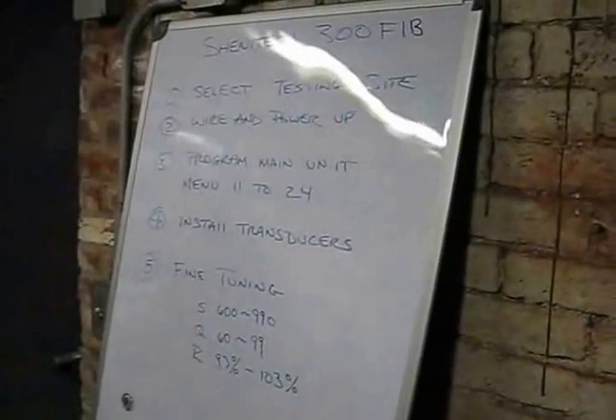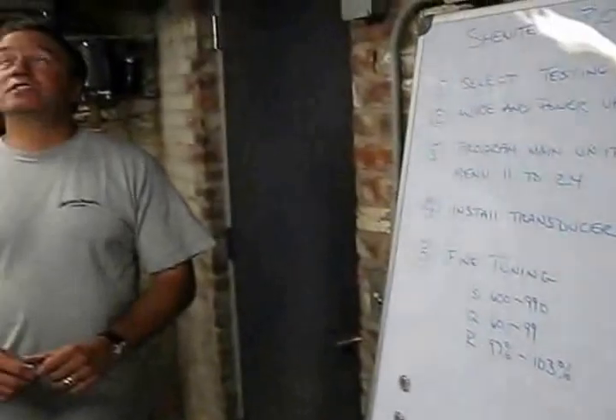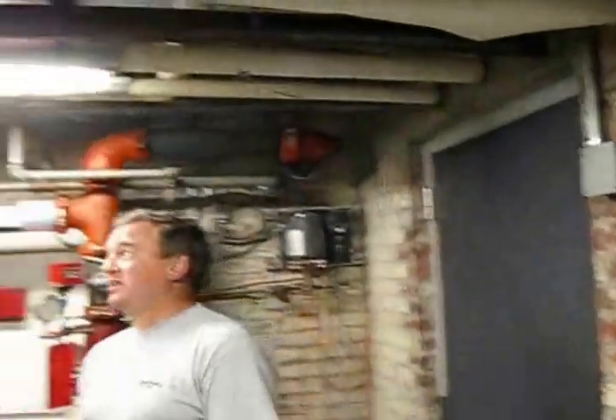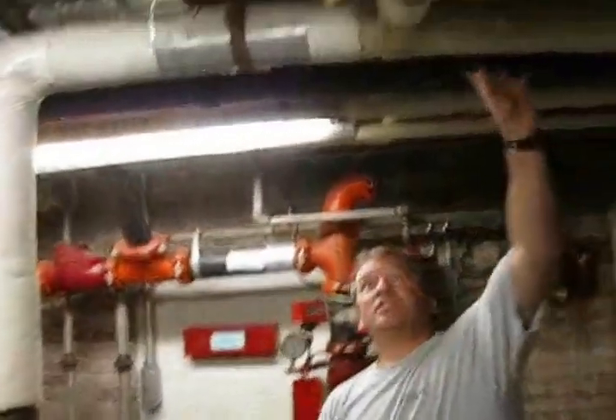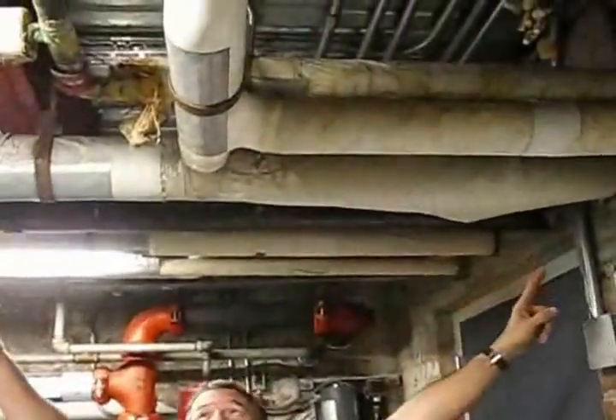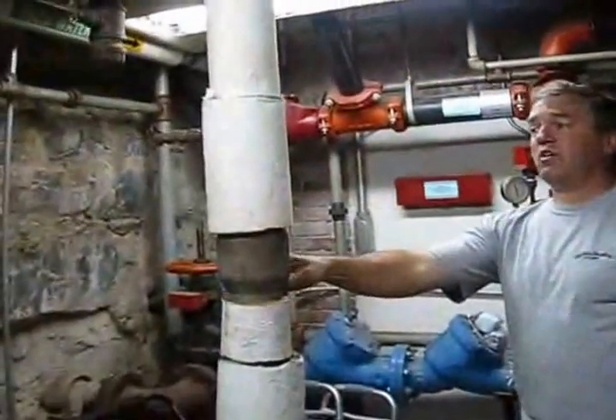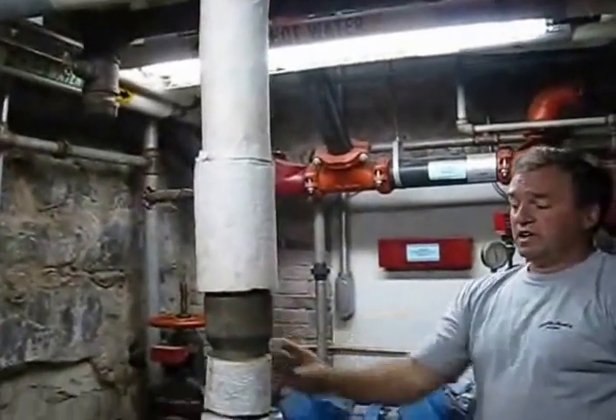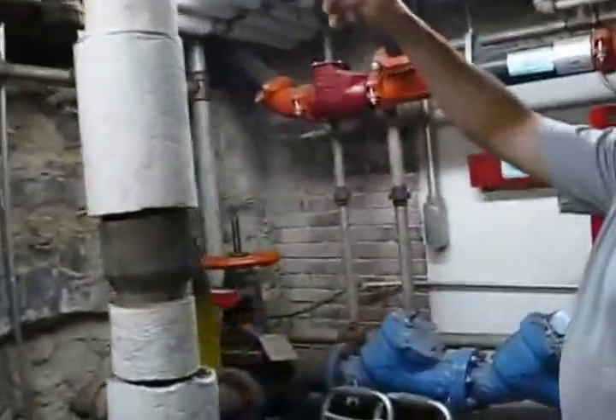The first step is selecting a testing site. We've chosen this location for the numerous pipes it has. We've chosen this section right here because it has a 15D run. You could have also chosen this section here because it does have a ball valve, but a ball valve is considered a straight run with a 15D.